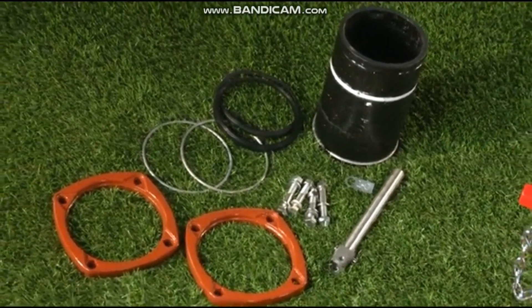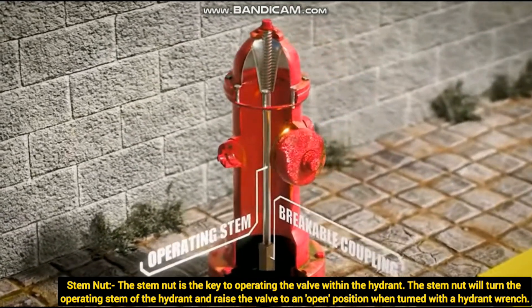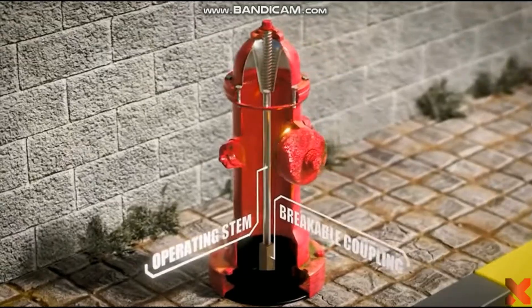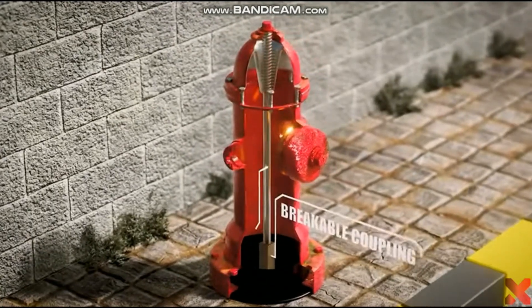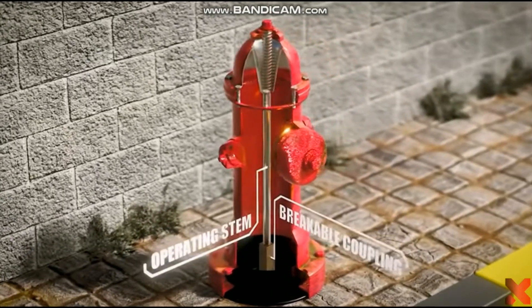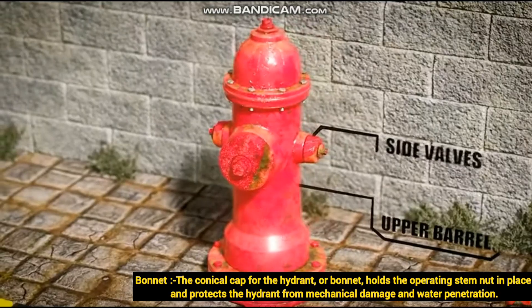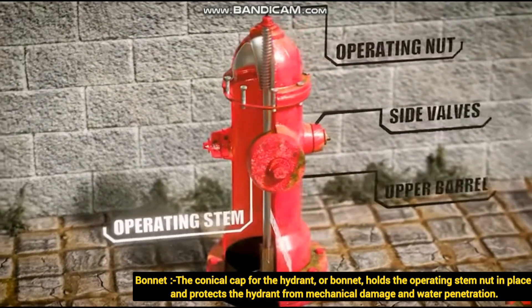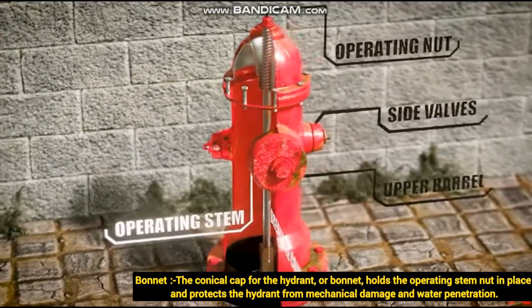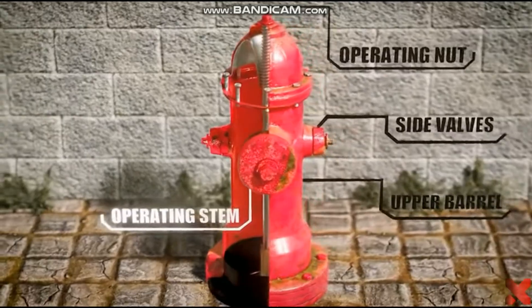Next we are going to see the important components of a fire hydrant. The first is the stem nut or operating nut — a vertical stem connecting the open/close valve with the operating nut, which limits water passage from the pipeline. The next component is the breakable traffic flange, designed to fracture when a 6,000-pound force is applied to the side of the fire hydrant during a collision. It is important to install the breakable traffic flange a minimum of 2 inches and maximum of 8 inches above finished ground level. The bonnet holds the operating stem nut in place, protects the hydrant from mechanical damage and water penetration, and includes side valves and upper barrel.